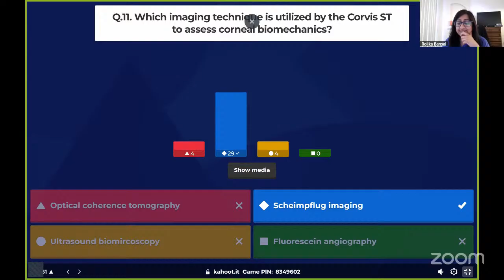So Corvis ST is basically a corneal biomechanical index test device, and this utilizes 2 parameters. It also takes into account the topography or the tomography and also the corneal hysteresis. On the right side of the image, we can see the corneal tomography and topography images that we are deriving from Pentacam or Scheimpflug imaging. So it is the Scheimpflug imaging that is utilized in the Corvis ST to capture the dynamic response to the air puff. This in toto gives us the assessment of the biomechanical strength of the cornea in question.